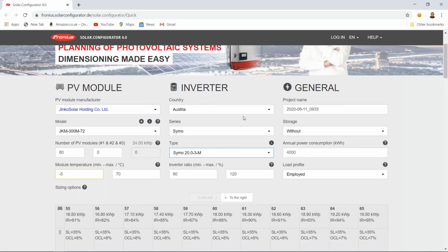And then once you're done with that, we now come to the inverter ratio, just like Mo earlier described. It can actually be lower than this or higher than this. And like we've presented to you from our previous webinars and data sheets, you can actually oversize our inverters up to 150%.